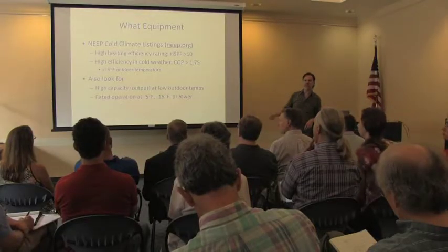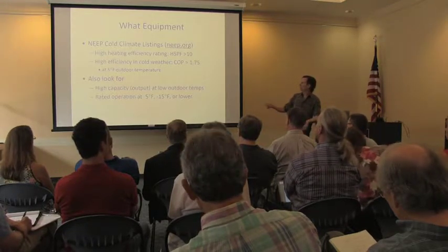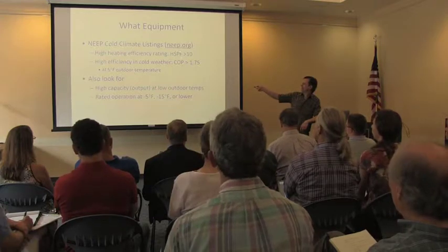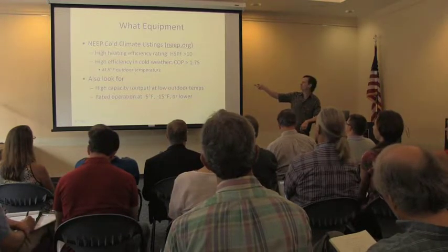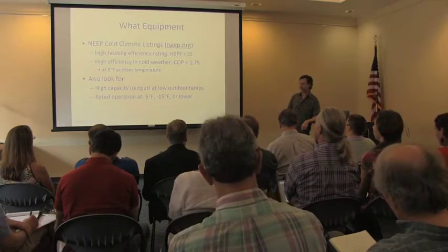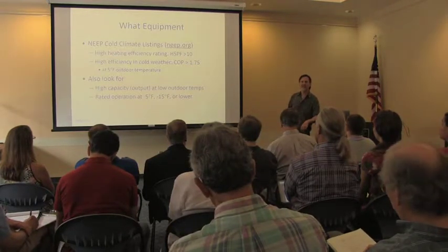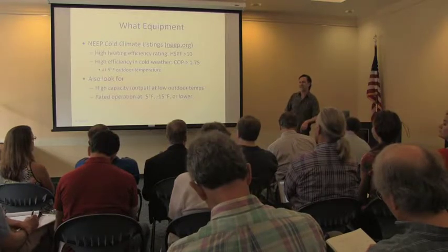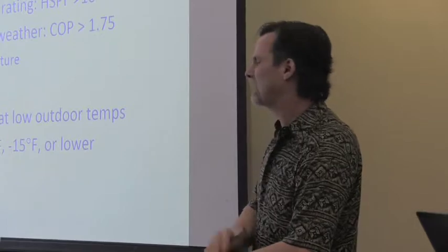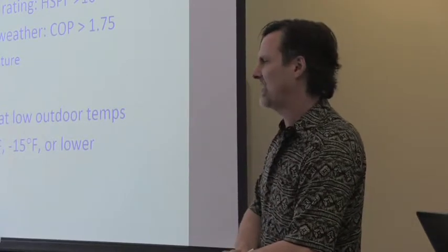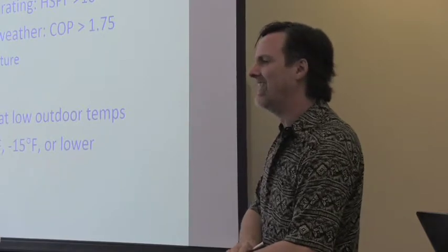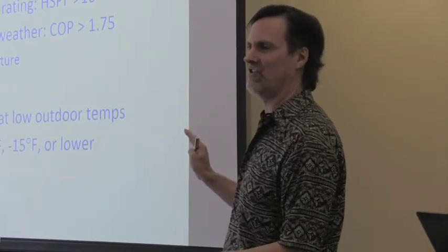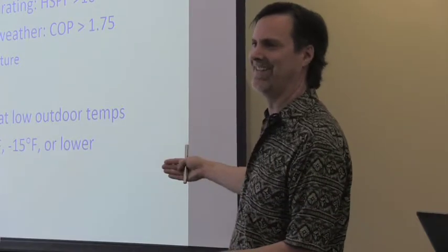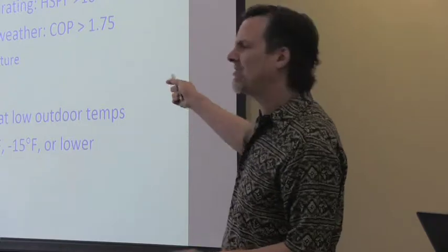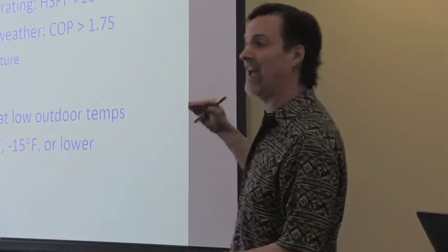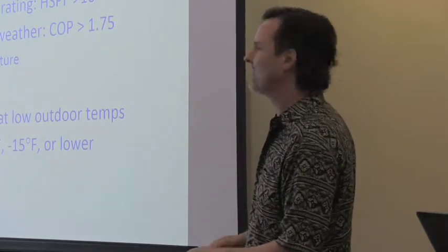They've put together a listing of cold climate heat pumps. So there are a few criteria. The HSPF, which is the standard DOE efficiency rating for heat pumps, has got to be greater than 10. That number isn't really meaningful, by the way. The HSPF rating doesn't actually represent the performance in this climate. I kind of liken it to the Volkswagen emissions test for measuring efficiency of heat pumps, except that unlike Volkswagen, they weren't doing it on the sly, right? This is actually required by federal regulation that all manufacturers have to test it this way. But it's still a benchmark. The more efficient systems still have higher HSPF ratings, and the less efficient systems have lower ratings.